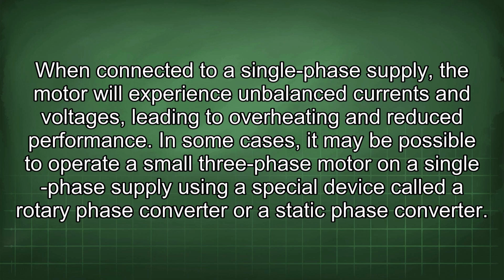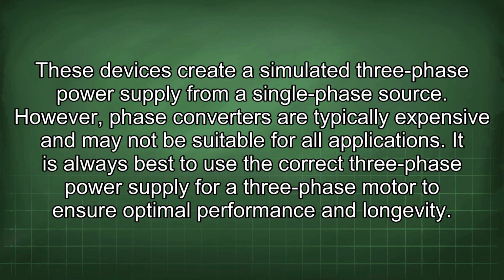In some cases, it may be possible to operate a small three-phase motor on a single-phase supply using a special device called a rotary phase converter or a static phase converter. These devices create a simulated three-phase power supply from a single-phase source. However, phase converters are typically expensive and may not be suitable for all applications.